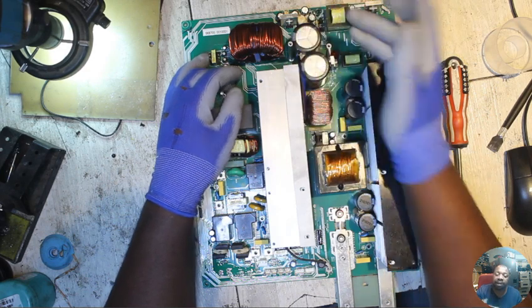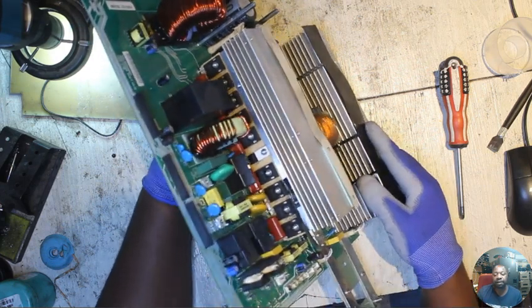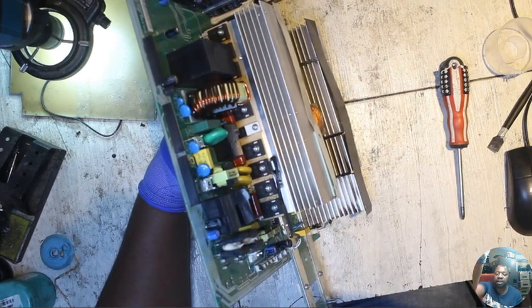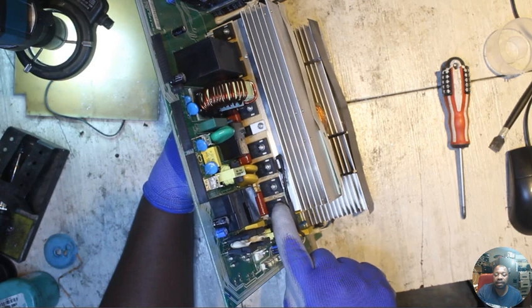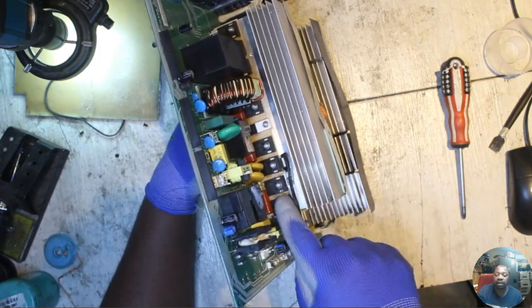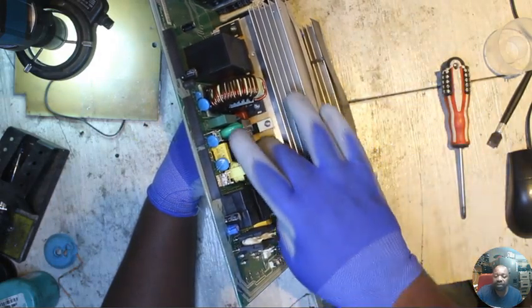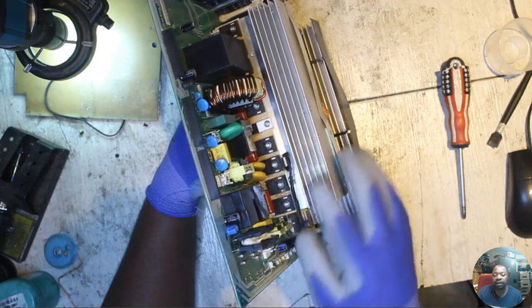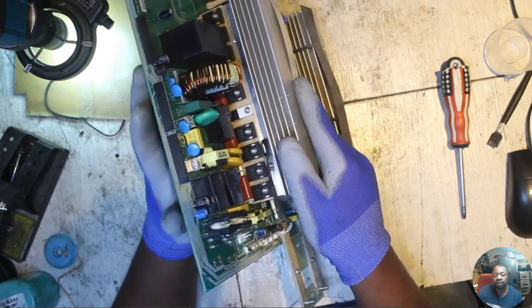The voltage is going to be 400 volts on the capacitors. On this side you've got your IGBTs - these are the most critical components on the inverter. These IGBTs change the 400 volts into AC. So with the high frequency inverter you rely mostly on these transistors, whereas with the transformer-based inverter you rely mostly on the transformer. We have to make sure the IGBTs don't get damaged - they are very fragile.